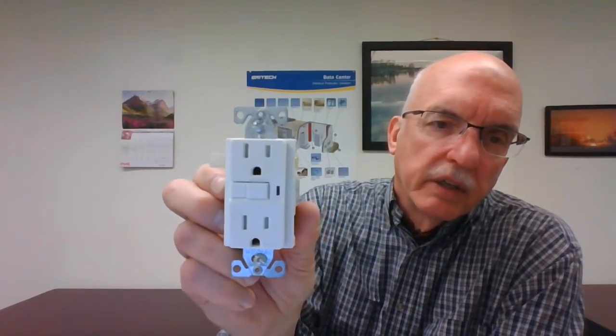It's got a test and reset button on it, and it's a chunky type of device, and you might have trouble fitting that into the box that's there. You may have to put an extension, like a wire mold extension ring, on over the original box to get something this deep to fit in there. So you only have two choices, basically. Option one is to install the AFCI receptacle, and you've got to make it fit, like I said, one way or the other.